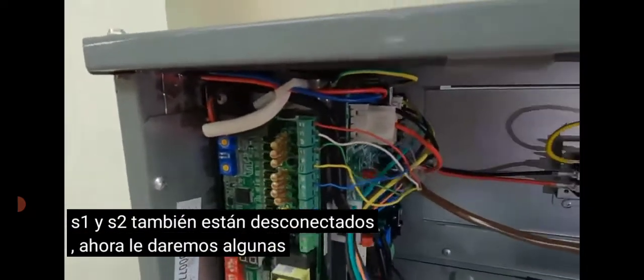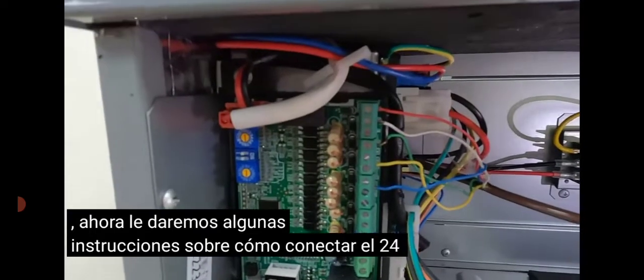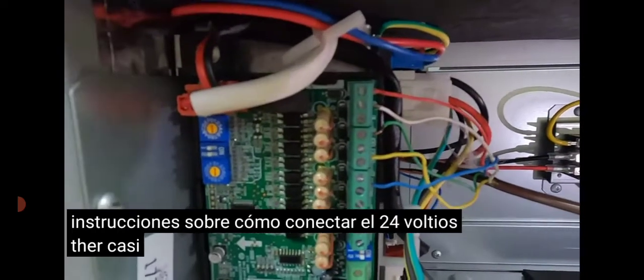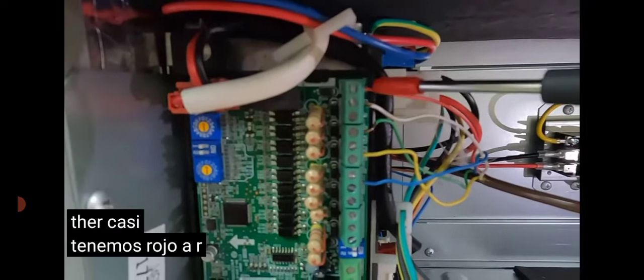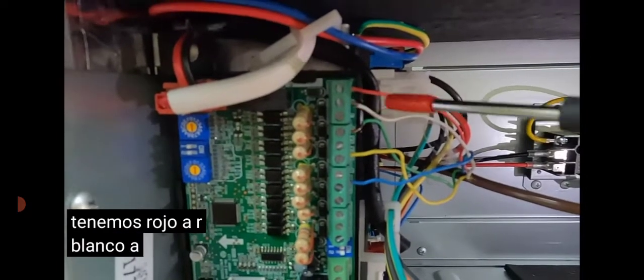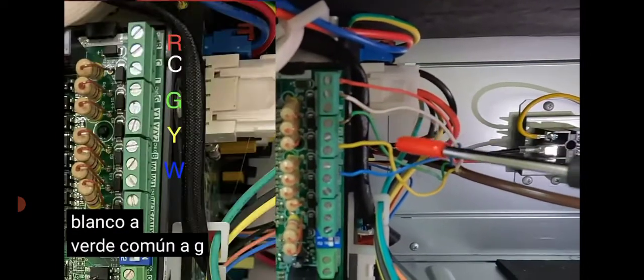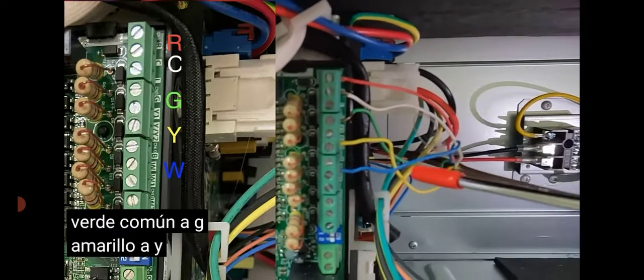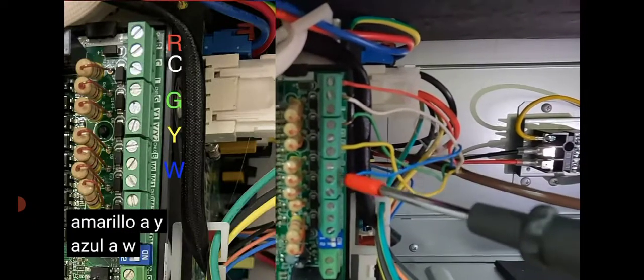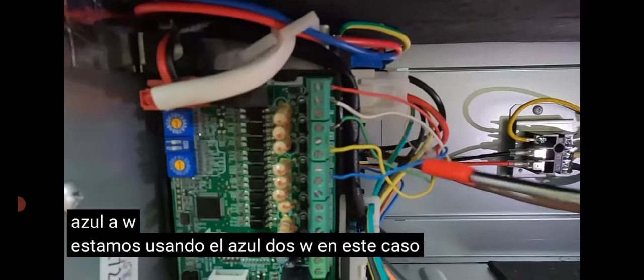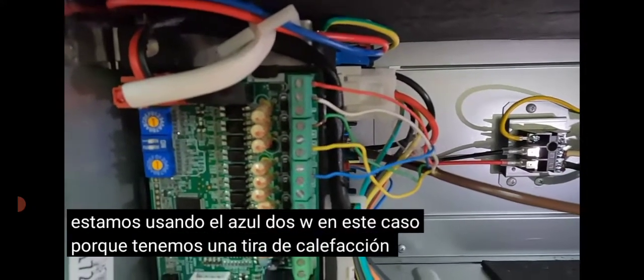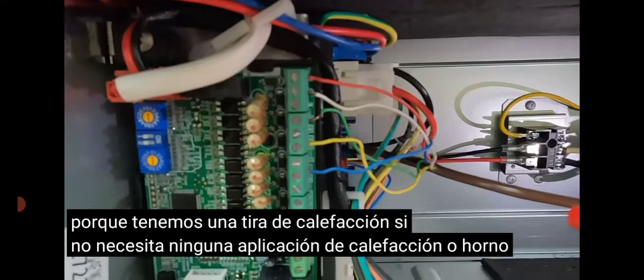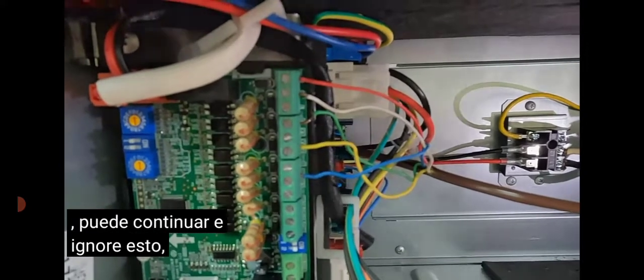We're now going to give you some instructions on how to wire the 24-volt thermostat. We have red to R, white to common, green to G, yellow to Y, blue to W. We're using blue to W in this case because we do have a heating strip. If you do not need any heating or furnace applications, you can disregard this.